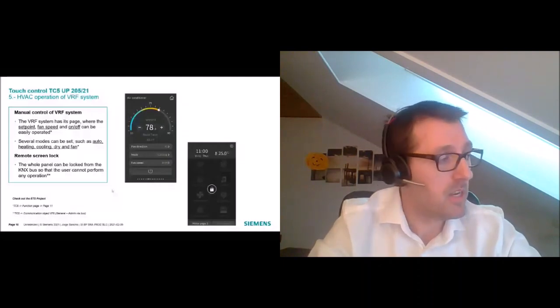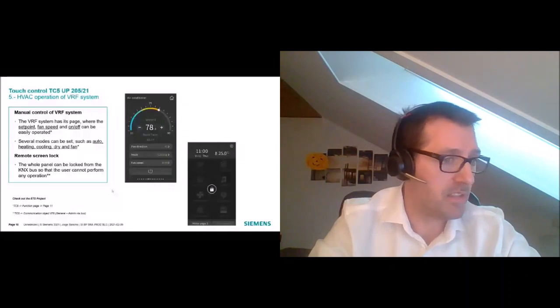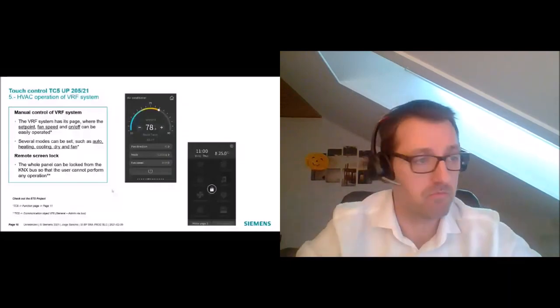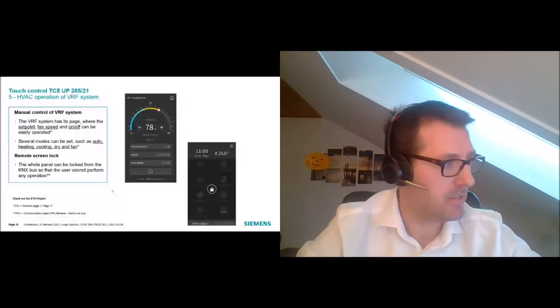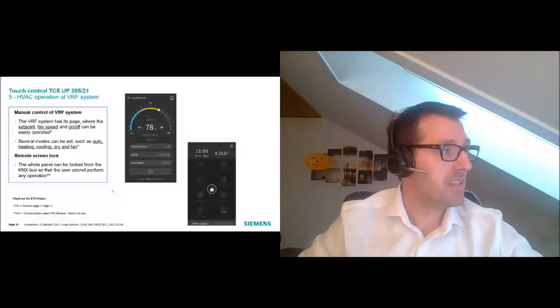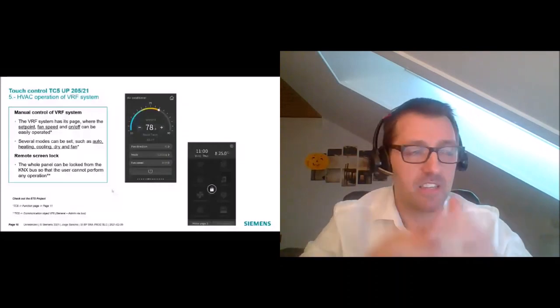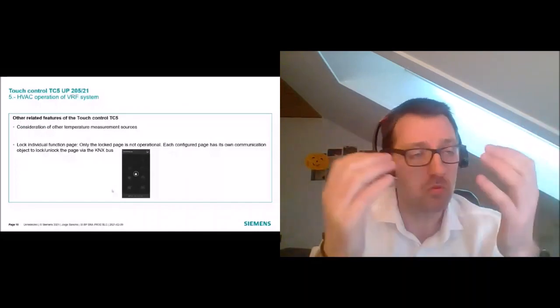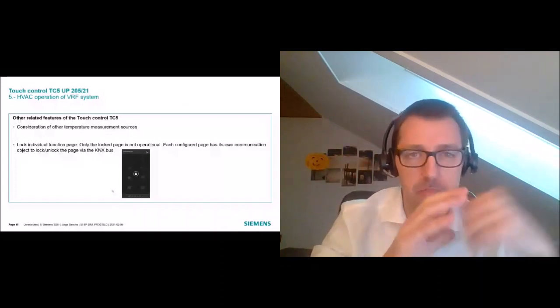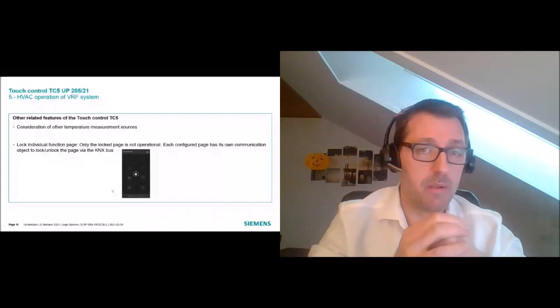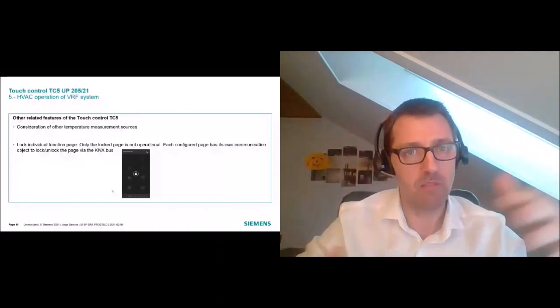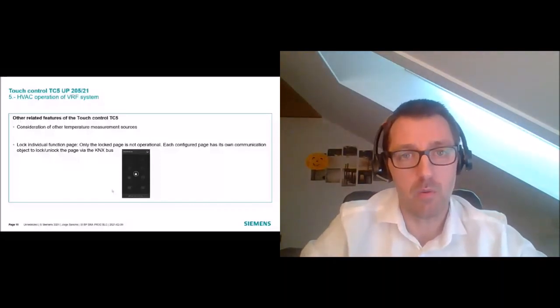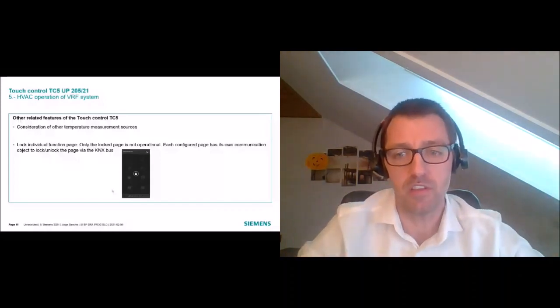Regarding the remote lock/unlock requirement, we have a communication object for that. Remotely, the customer can lock and unlock the whole panel, which can be very useful in many applications. Other related features: each page has its own communication object, so you don't have to lock the entire panel — you can choose to lock only the lighting page, the VRF page, or any other, while keeping the rest unlocked. Each page of the TC5 has its own communication object for locking and unlocking remotely.